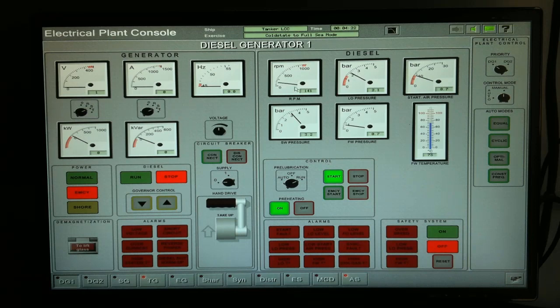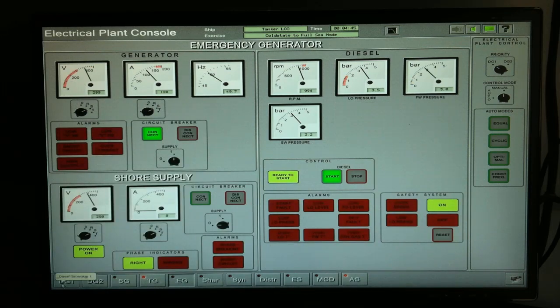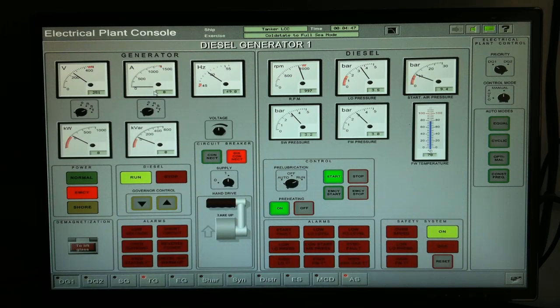RPM will build up to around 997 RPM. Once you have 997 RPM, voltage and hertz will accumulate. Once you have voltage and hertz accumulated, supply your circuit breaker and then connect to the main bus bar. Once you connect to the main bus bar, all the electrical load from the emergency generator will be transferred to generator number 1.